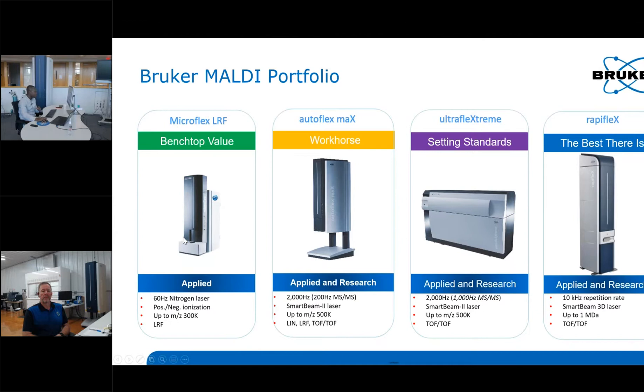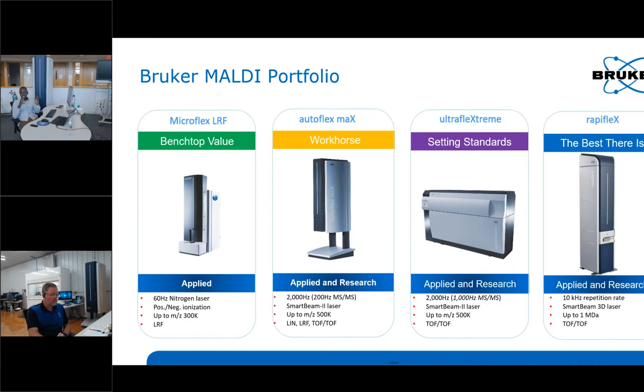Next up is the AutoFlex Max, which has a vertical setup. This is actually the instrument we're going to be using for today's demo — you can see it right next to me. This is an all-around MALDI workhorse that can do almost anything, including top-down sequencing, MS/MS experiments, and MALDI imaging.